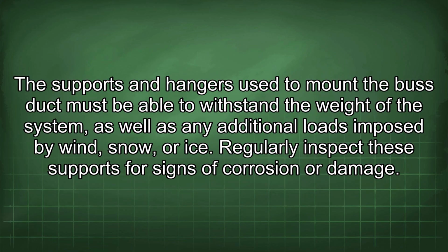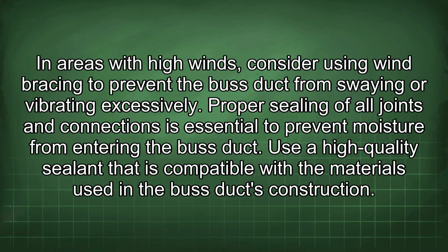The supports and hangers used to mount the bus duct must be able to withstand the weight of the system, as well as any additional loads imposed by wind, snow, or ice. Regularly inspect these supports for signs of corrosion or damage. In areas with high winds, consider using wind bracing to prevent the bus duct from swaying or vibrating excessively.